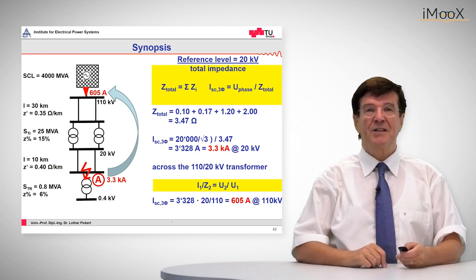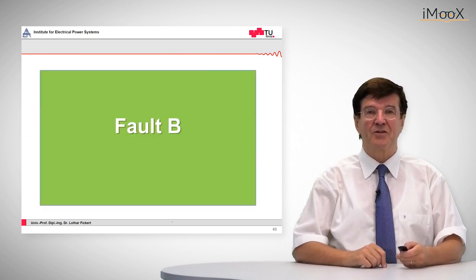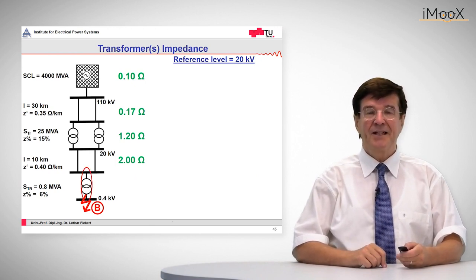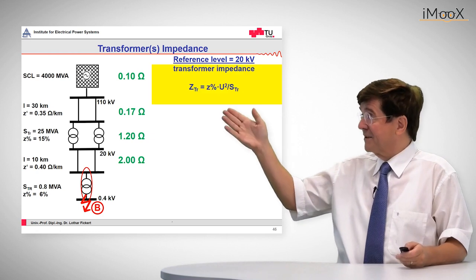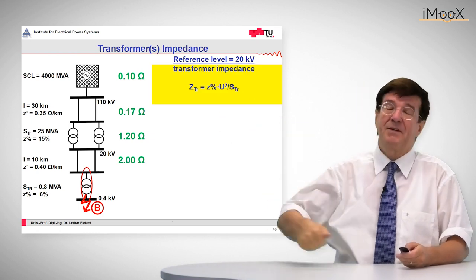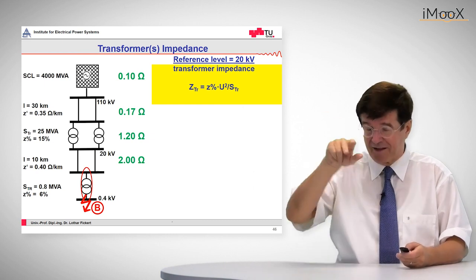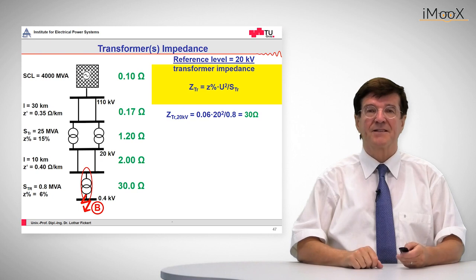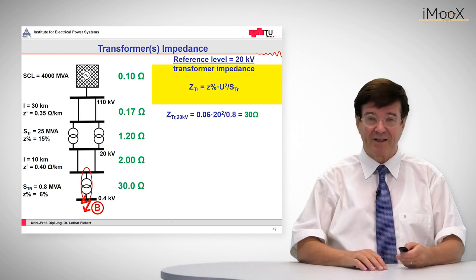The next one is fault B, which is the fault on the low voltage side of this distribution transformer. So again we calculate the impedance of the transformer, which is the product of the percentage impedance times U squared divided by the apparent power of the transformer, and the result is 30 ohms on the 20 kV level.